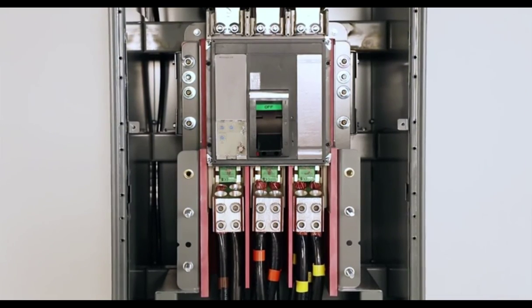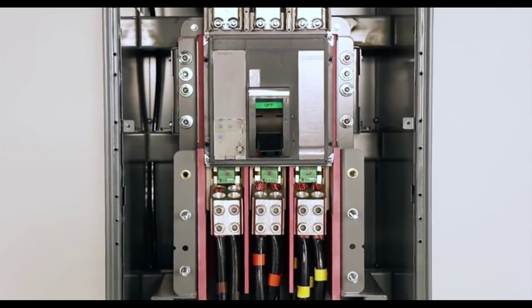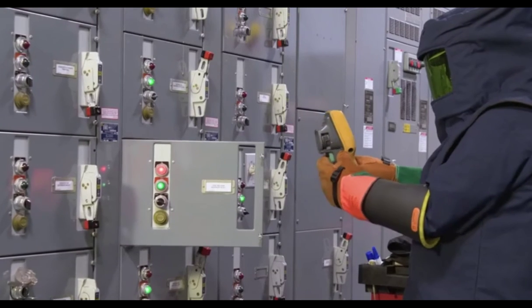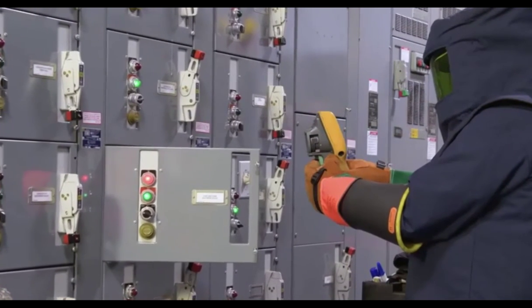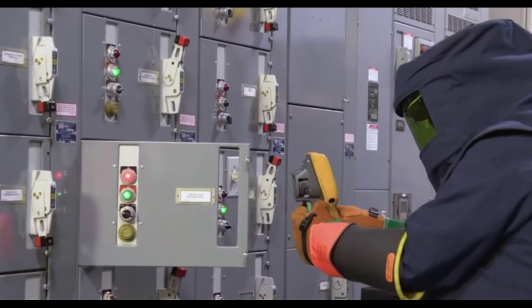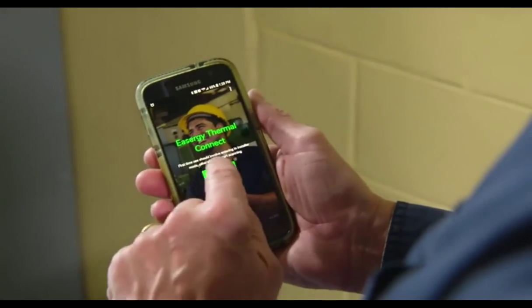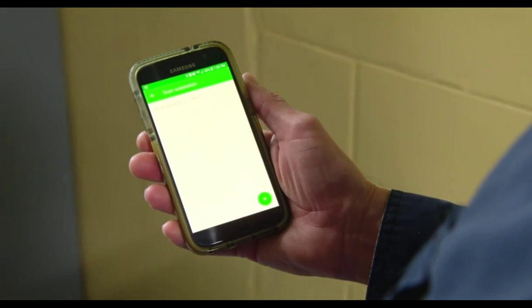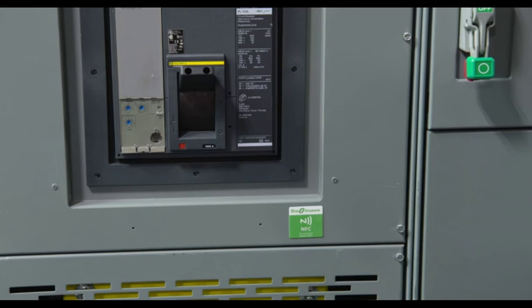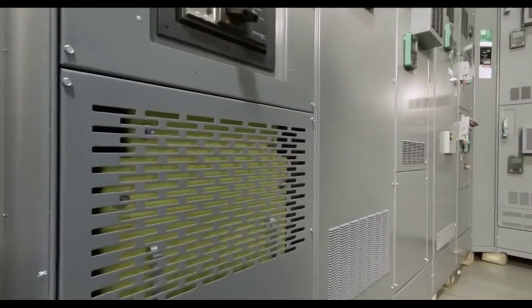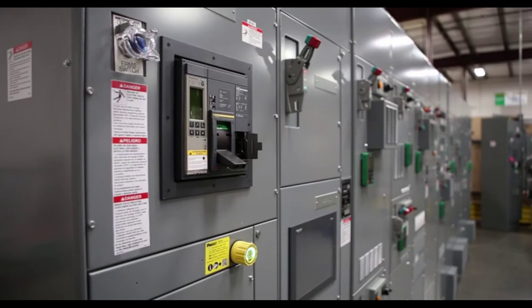Another feature of the ArcBlok motor control centers is wireless thermal sensors. These sensors continuously monitor the temperature of the line terminals, making it unnecessary to perform infrared thermography in this area, and thus avoid exposure to the line conductors. It can be easily read on your smartphone using our app and dongle while standing outside the arc flash boundary. Just scan the NFC tag on the equipment, open the app, and our wireless feed will update your screen to obtain the latest temperature data from your equipment while you remain safely beyond the arc flash boundary. Whether you are updating your existing MCC or buying a new one, get a new level of arc flash protection with ArcBlok technology from Square D by Schneider Electric.